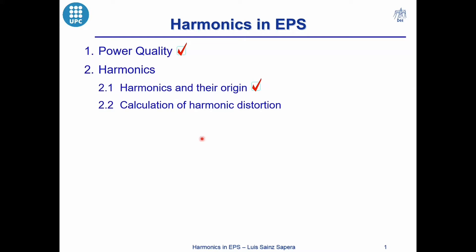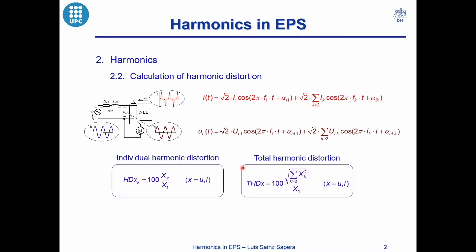For this we have two ratios: the individual harmonic distortion and the total harmonic distortion. Imagine that we have a current and a voltage distorted with the fundamental waveform and the harmonics. The individual harmonic distortion is determined for each harmonic, and it is the ratio between the corresponding root mean square value of the harmonic and the root mean square value of the fundamental waveform. This ratio provides an insight about the weight of harmonics on the waveform distortion.